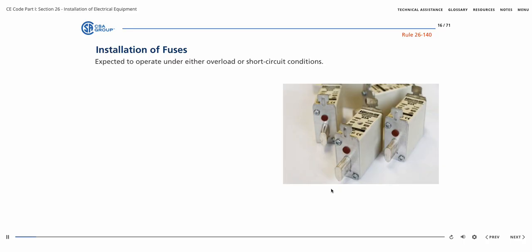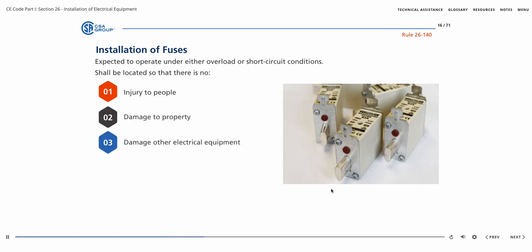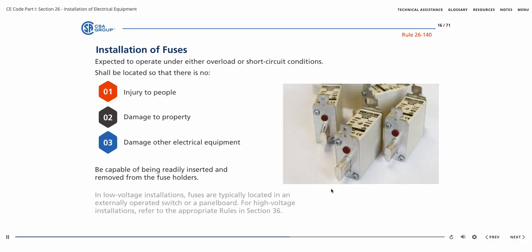A fuse is expected to operate under either overload or short circuit conditions. Rule 26-140 requires fuses to be located so that there is no injury to people, damage to property, damage to other electrical equipment, and be capable of being readily inserted and removed from the fuse holders. In low voltage installations, the fuses are typically located in either an externally operated switch or a panel board. For high voltage installations, refer to the appropriate rules in Section 36.